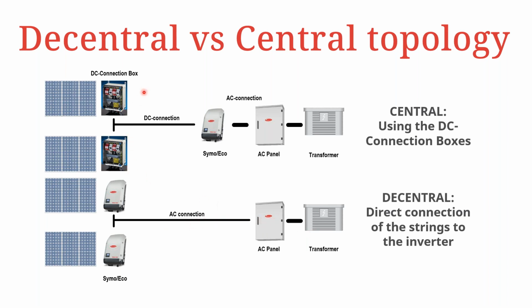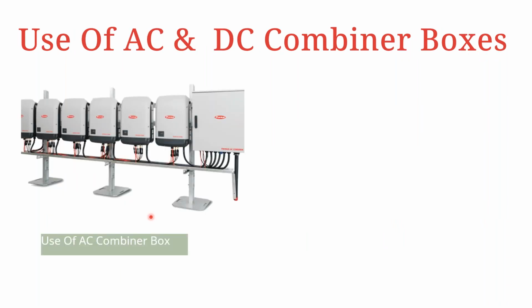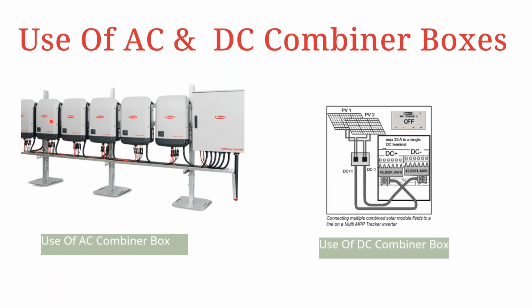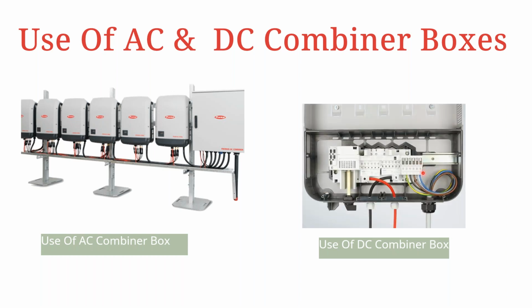So the advantage in the central topology is that you can save a bit of cost on the AC cabling, and on the DC side for the central design, you can also minimize the power losses because the DC power is traveling quite a short distance. It's also possible to use the AC combiner box, as we can see here, depending on how many inverters you have connected together. So if this, for instance, is a Fronius SolarNet ring, then all these 6 inverters would be connected to 1 AC combiner box. And then on the DC side, once you have the DC combiner box, like we mentioned before, you do require the DC connection kit within the inverter that is able to split this power to all the terminal connections, DC plus or DC minus, of the inverter, as we can see in this photo.